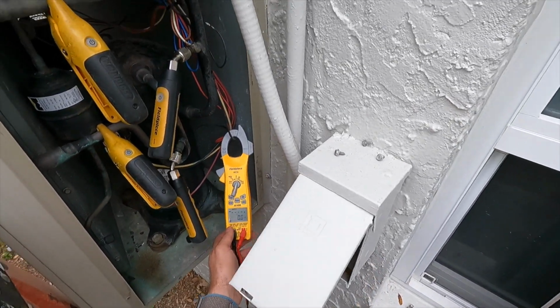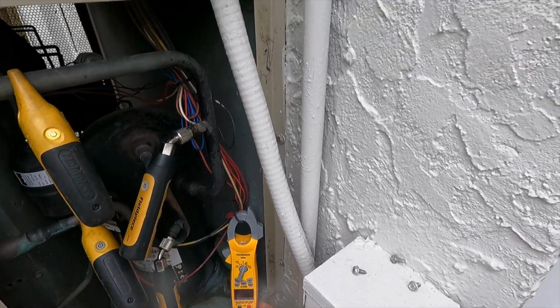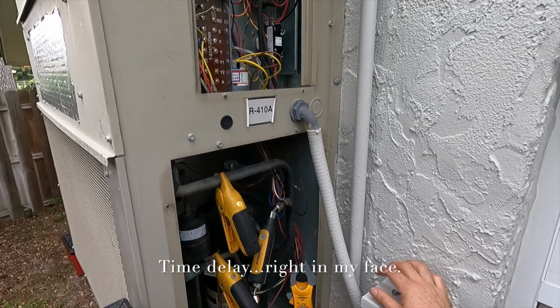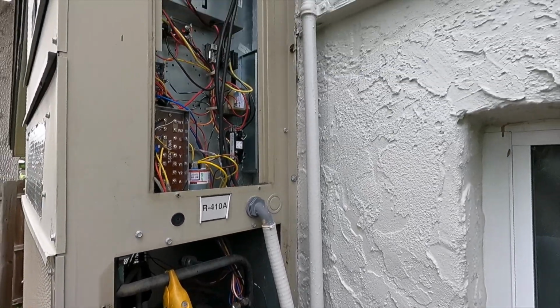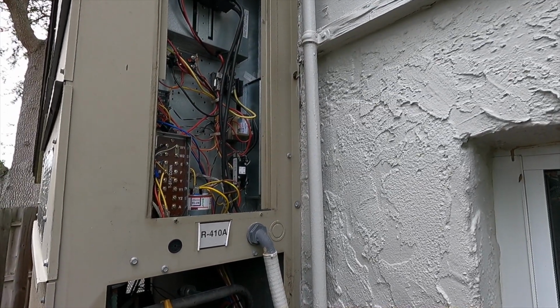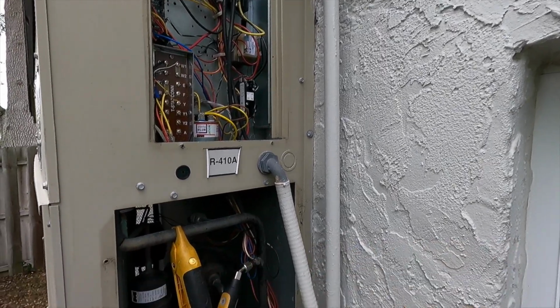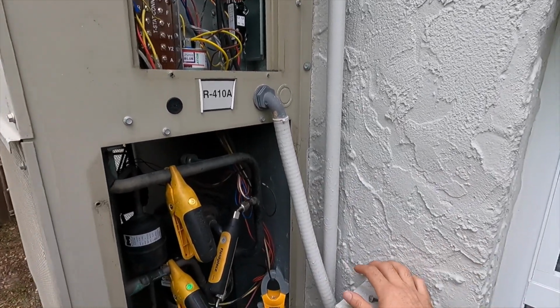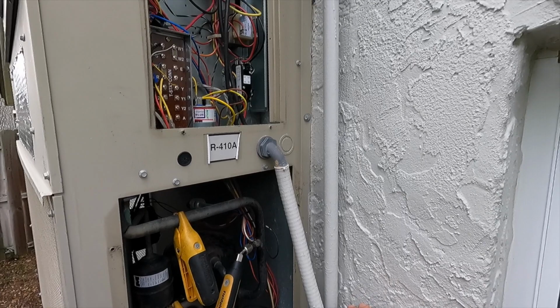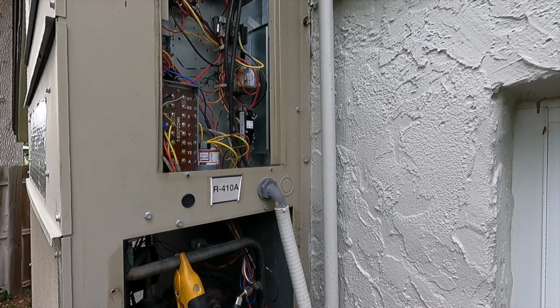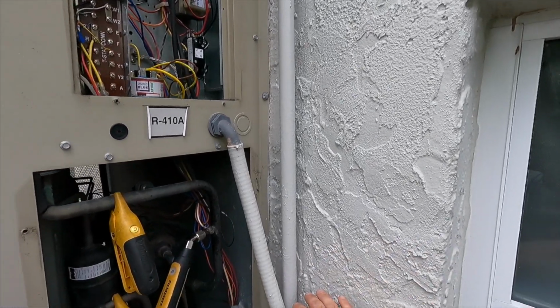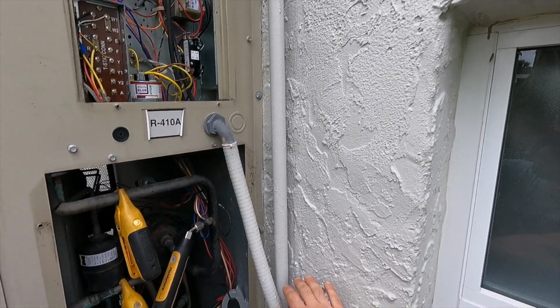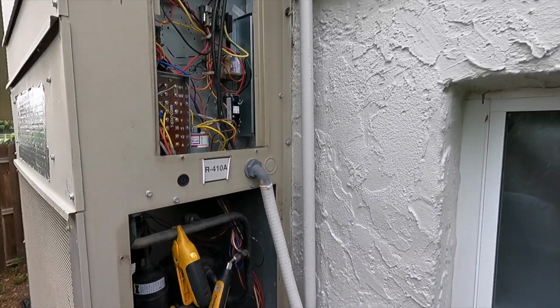Oh, that's not going to quite work. So we're going to have to wait for that time delay on that thermostat. He must have the thermostat wired for power from the unit. So killing the power to the unit effectively sets a 5-minute trip on that start. So I'm going to go ahead and stop the video for now, and once we get that lock rotor amp draw, I will take a look at that. So just something to show here.